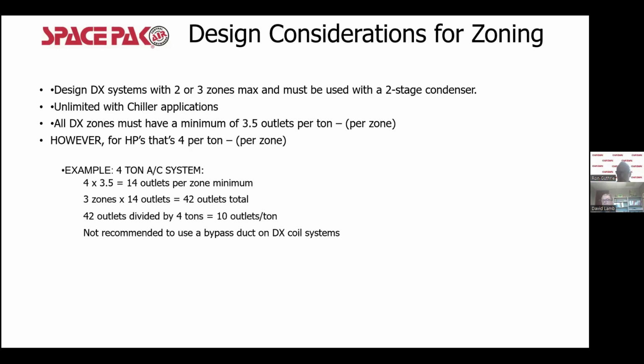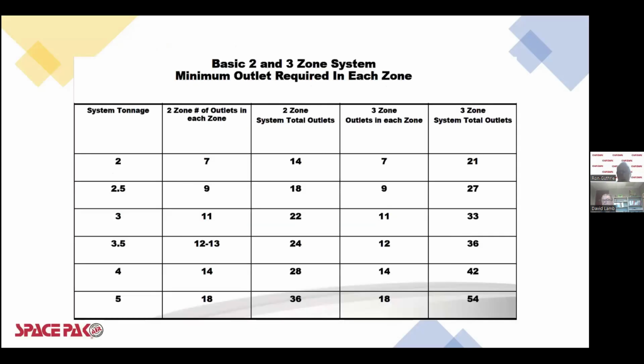If you're using 3 zones or 2 zones that aren't sized the same, then you're going to have to add outlets, and how many outlets you add is going to be determined by using this equation here. Okay, so keep that in mind. This chart is in the downloads for today, in what we call the tips brochure. If you look here, for 2 zones in a 2-ton system, that's 7 per zone. You come up with 14. Well, you're going to have 7 outlets per ton anyway.